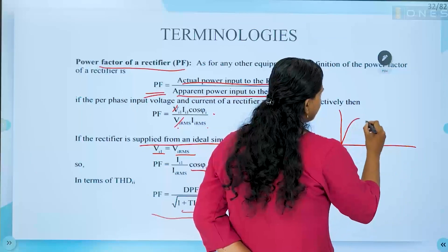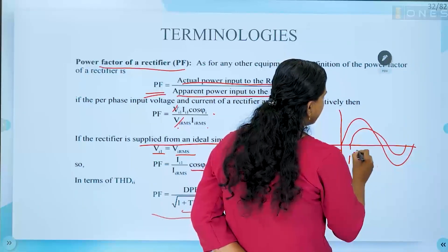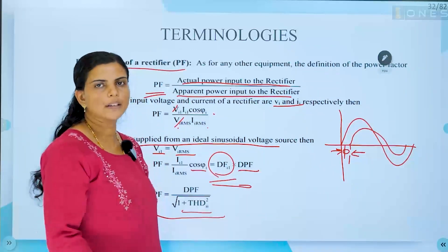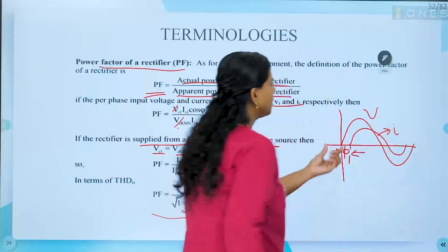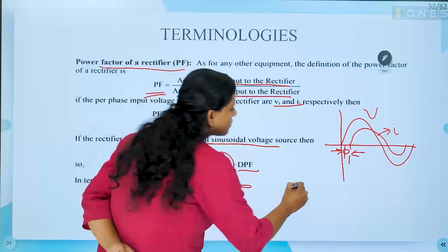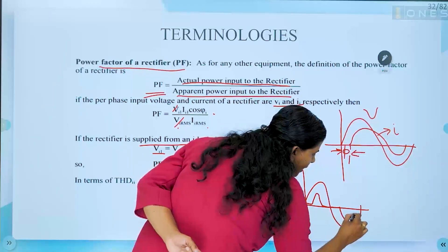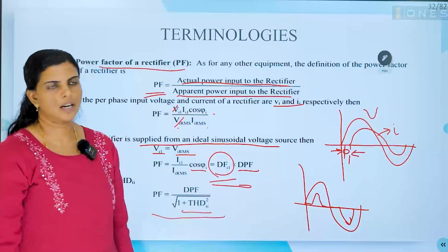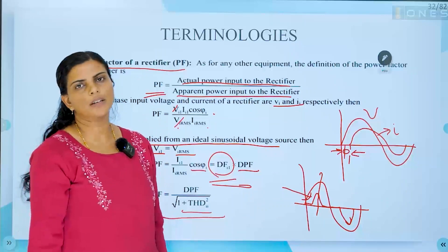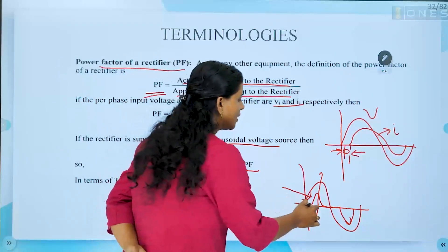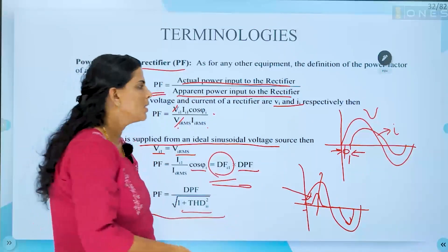We can find the balance difference between cos φ and actual power factor. Suppose we are getting a waveform — this is the voltage, and this is the current. Will you say the power factor is 1? The displacement is zero phase shift, but there is distortion factor. So power factor cannot be 1. Though there is no angular displacement and the current and voltage are in phase, due to distortion the power factor is not 1.